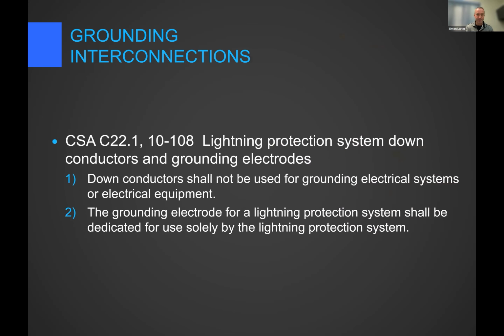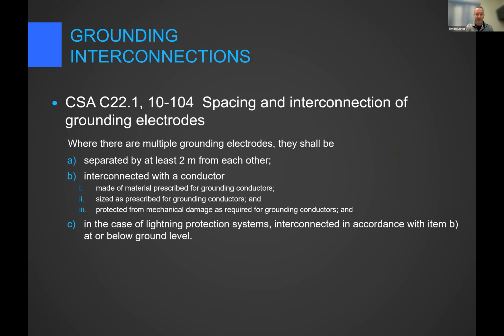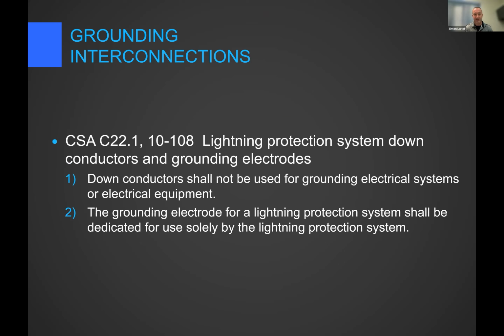It's supposed to be made of a material prescribed for grounding conductors, sized as prescribed, deliberately interconnected. All that other incidental contact anywhere else on the building, that's not the thing. That's not what we call our grounding interconnection.